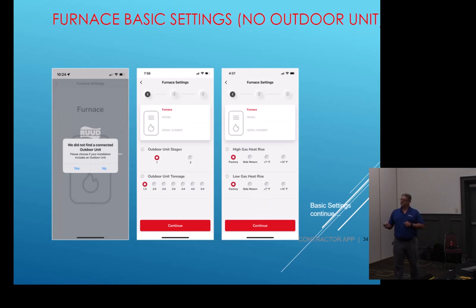So this one said we did not find a connected outdoor unit. So you could have a Bluetooth air handler or furnace inside and a regular 14 SEER condensing unit outside, right? So that 14 SEER is not Bluetooth compatible, right? Doesn't have a Bluetooth board in it. You can still use it with that system, but then when you go in for the furnace or air handler, you need to set it up and tell it whether it's 1 or 2 stage, what tonnage it is, so it knows how much air to blow for that size unit outside. It just wants to know a little bit of information about it, okay? This really takes seconds to do on your phone. We talk about it a lot, but it takes seconds to do.